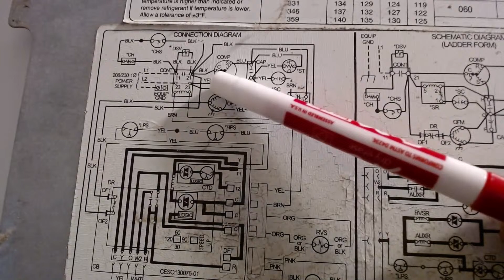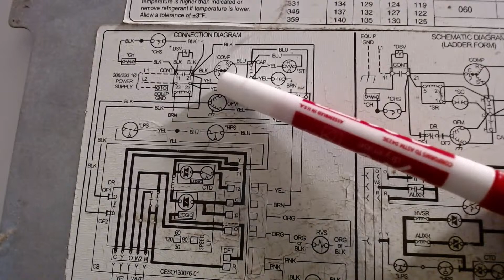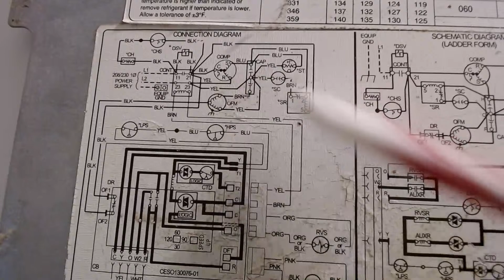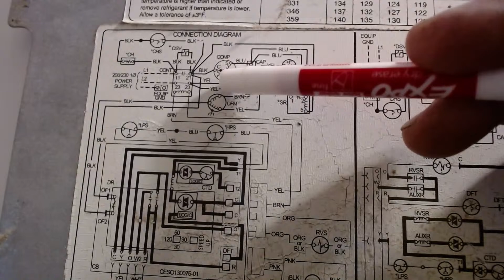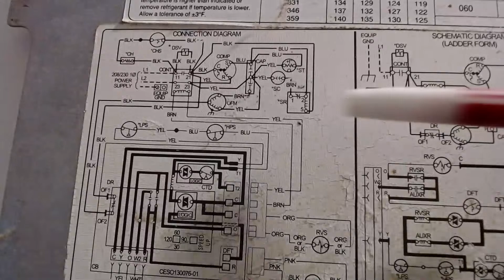And you can see the temperature icon right there, relay switch. It's in the common, in the winding. So when that winding gets hot, it opens up. That is why a lot of us, when we're testing our compressors out, our common winding always opens up when it overheats, because it has this built-in temperature probe into the winding, into your setup, into your compressor. It's right there. That's why everyone's like, why is it always my common side? Well, that's why.